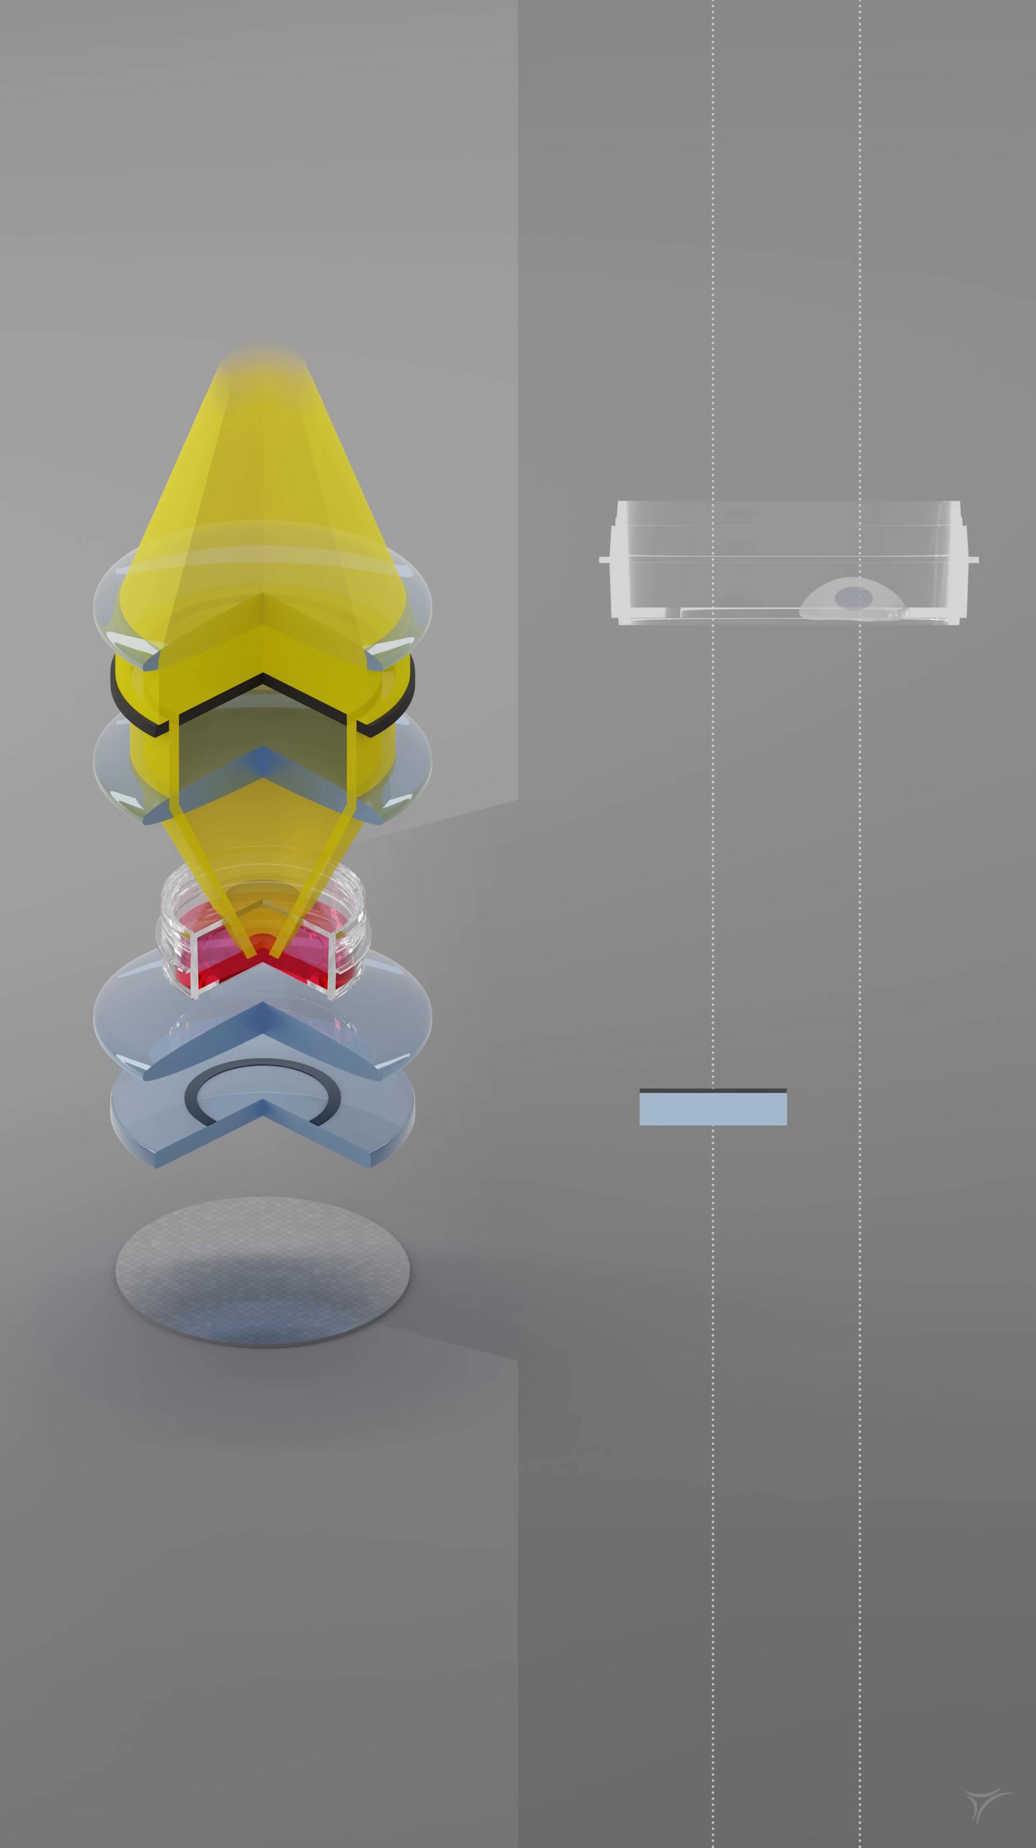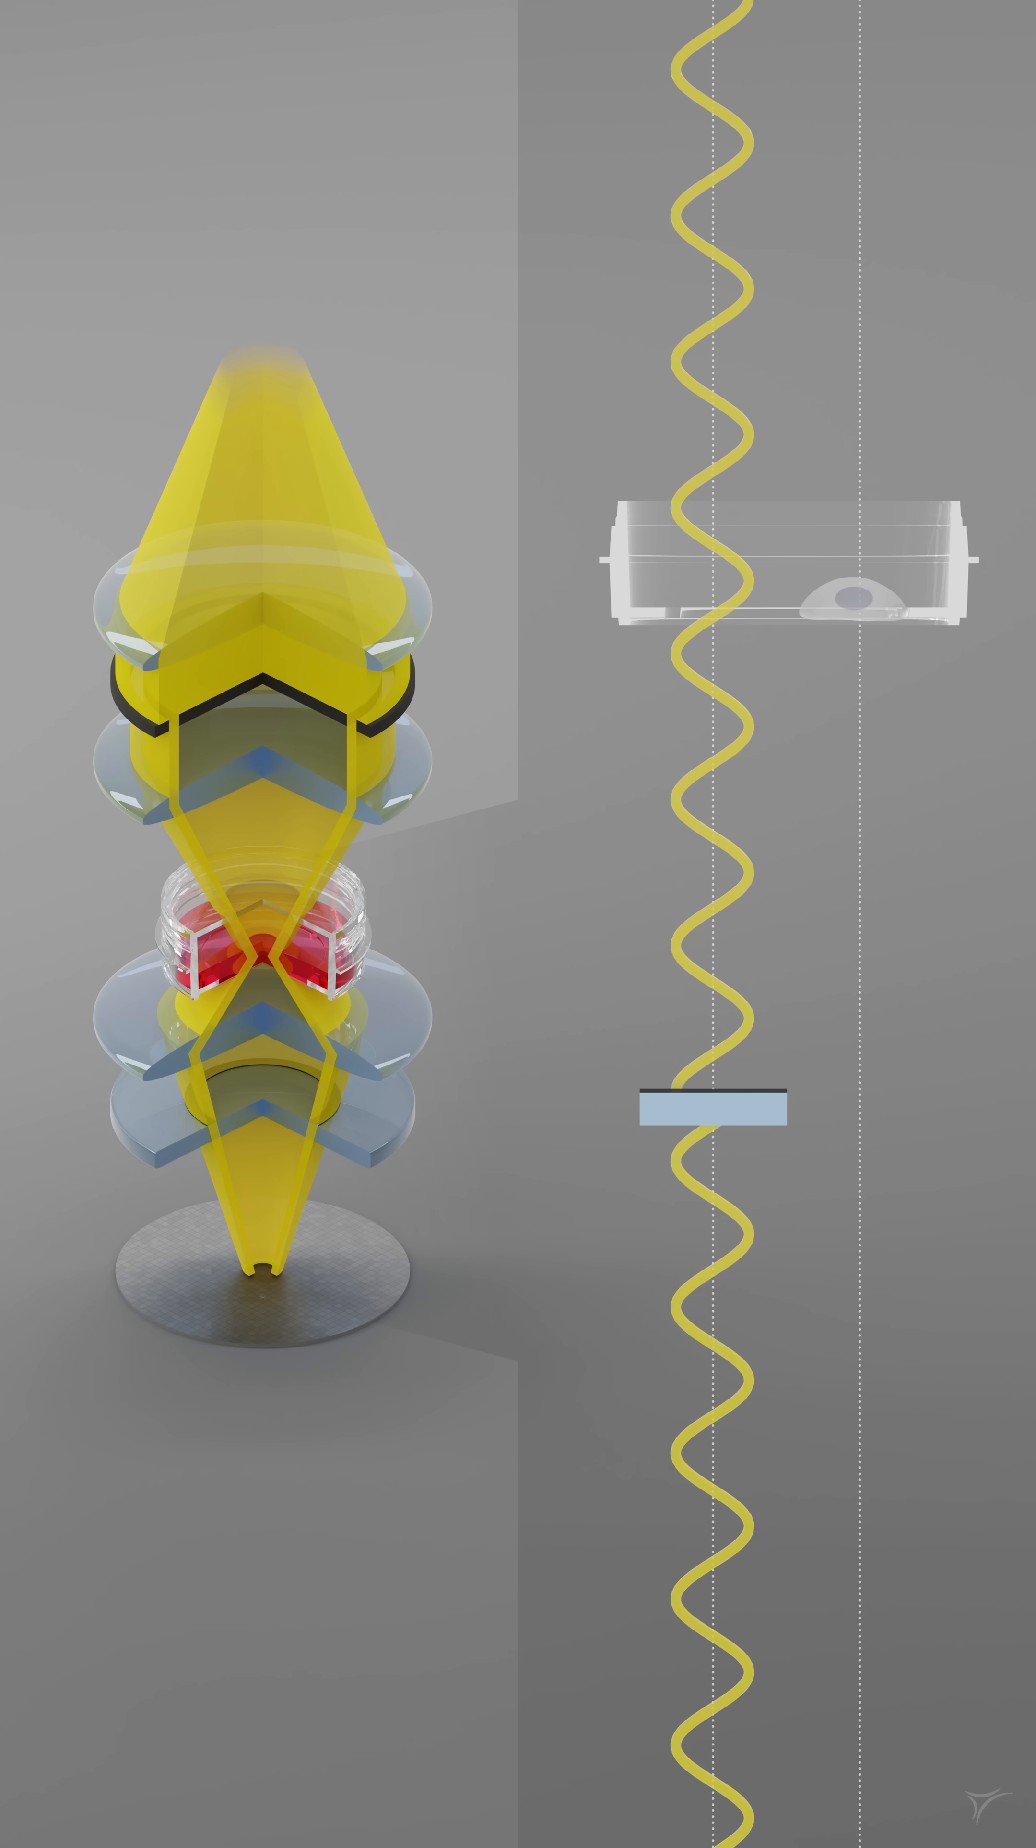The annular ring structures the light by creating a tube-shaped illumination that is focused on the sample. The light not passing through the sample remains unaffected while keeping its tube-shaped structure. This allows a precise transfer through the phase ring where a defined phase shift is applied.